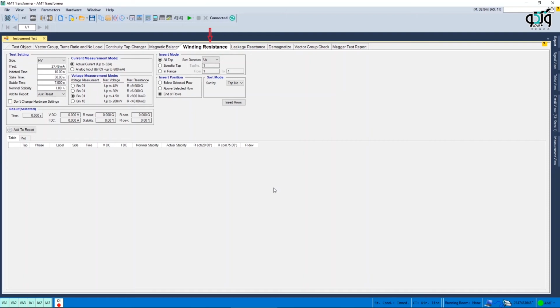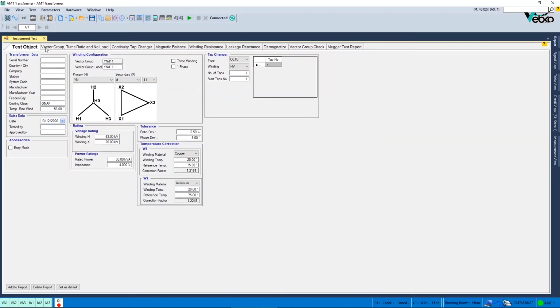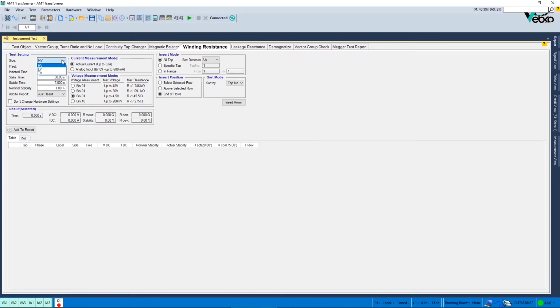Winding resistance tab. One of the most common and important tests of transformers is the winding resistance test. In this test, the DC resistance, or R, is calculated by dividing the voltage measured through the binary inputs by the injected current. To perform this test, first you need to specify the primary or secondary side, among HV and LV, in the side field. Note that if the transformer has 3 windings, TV is added to the 2 mentioned options.